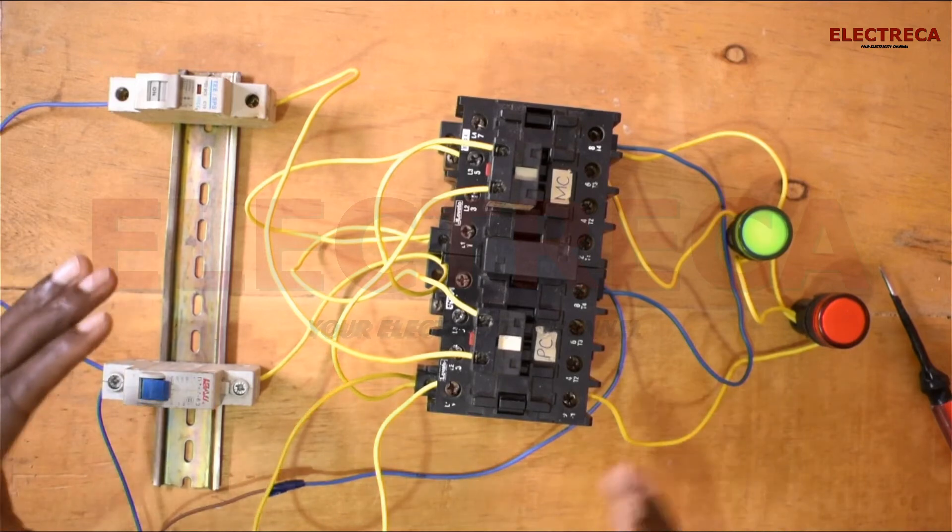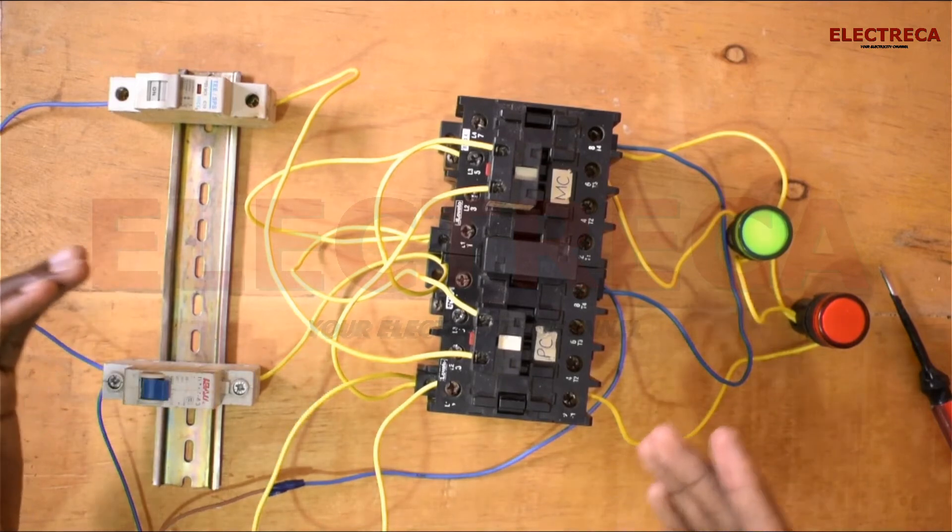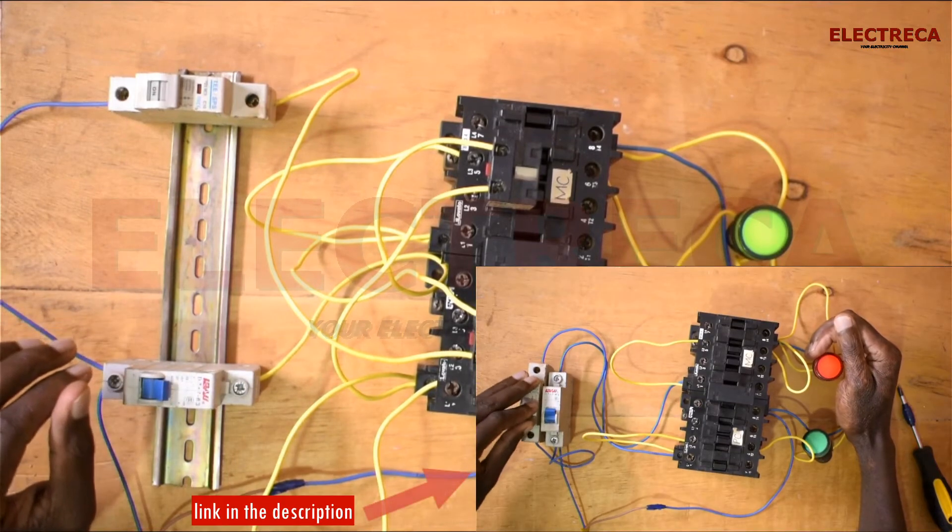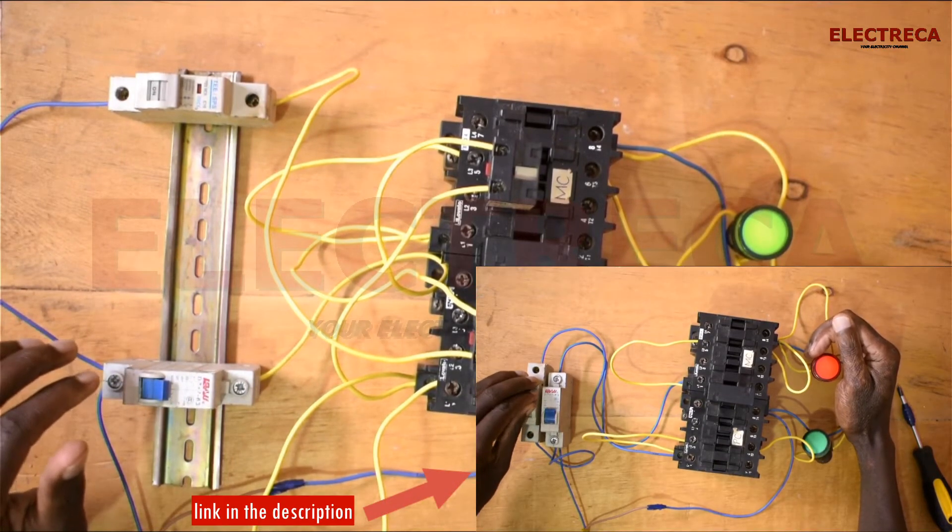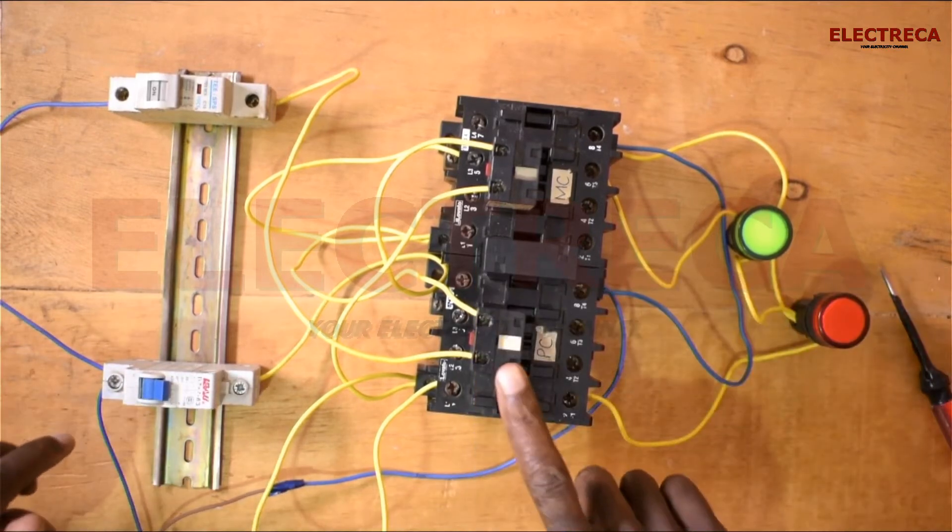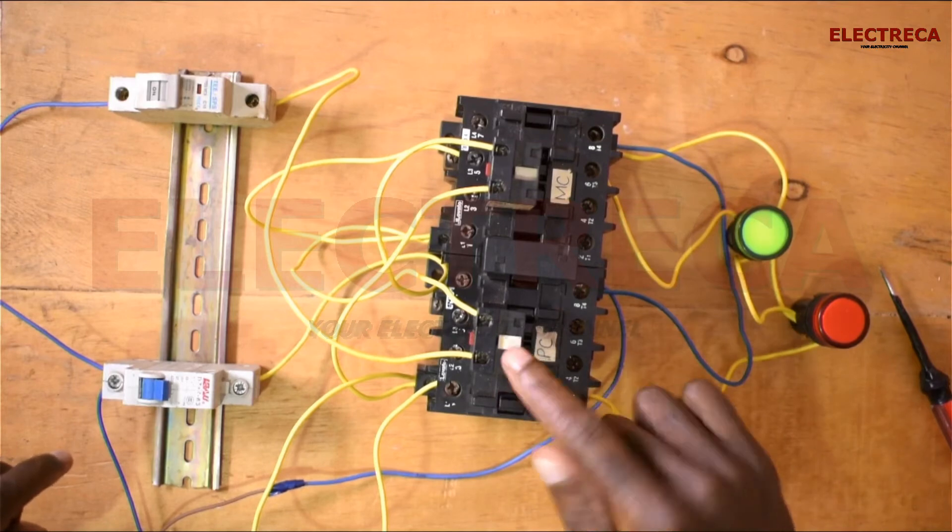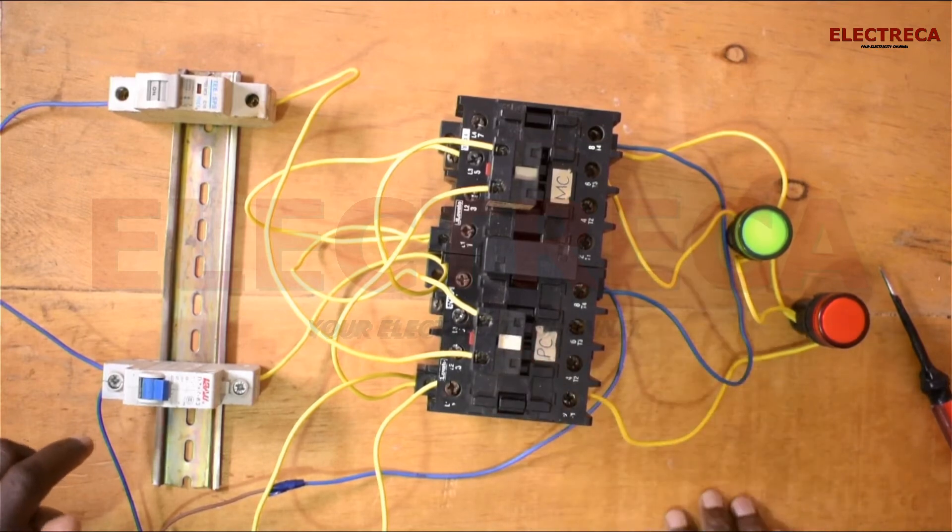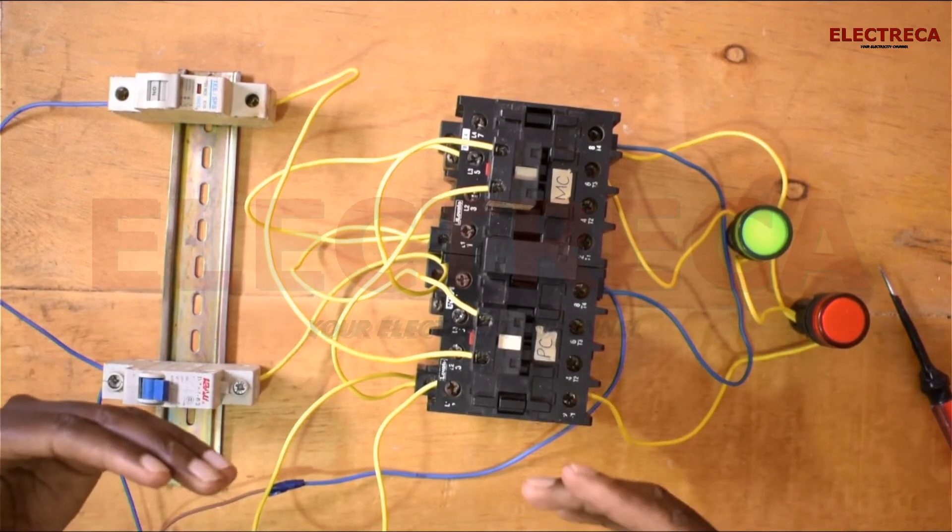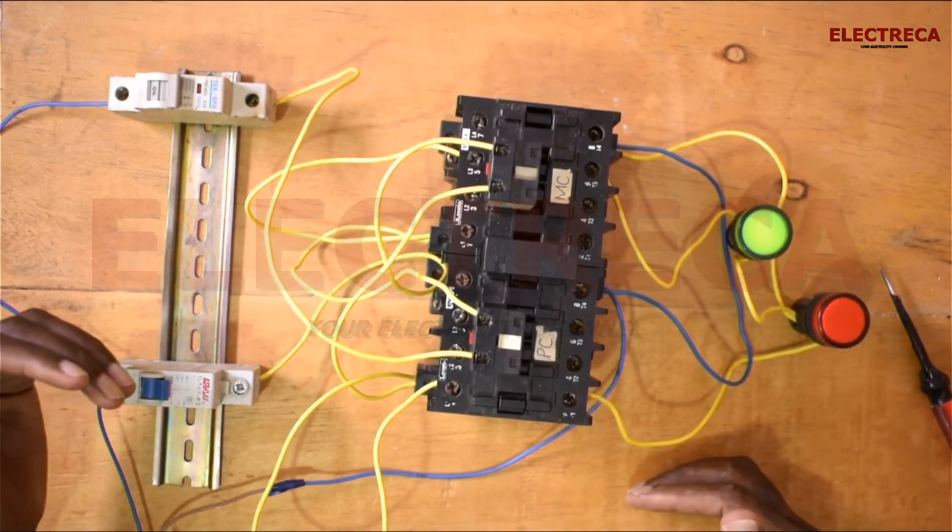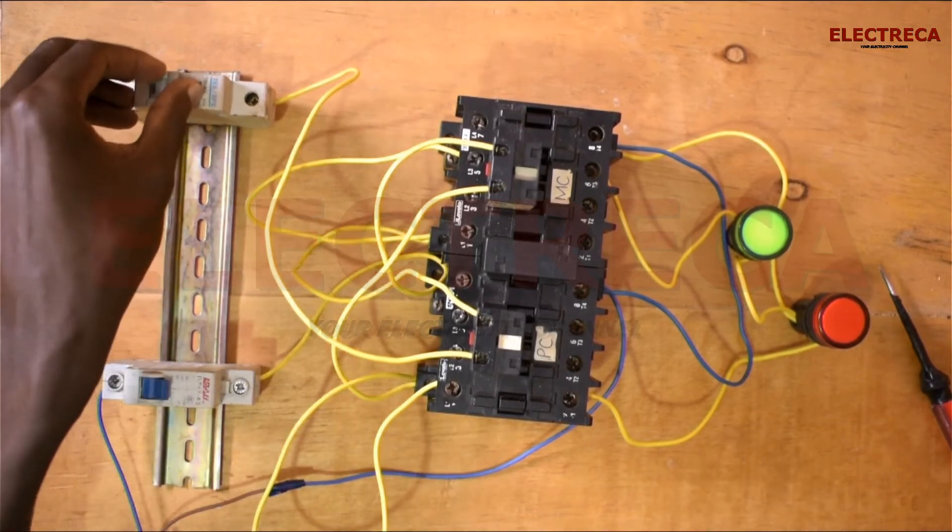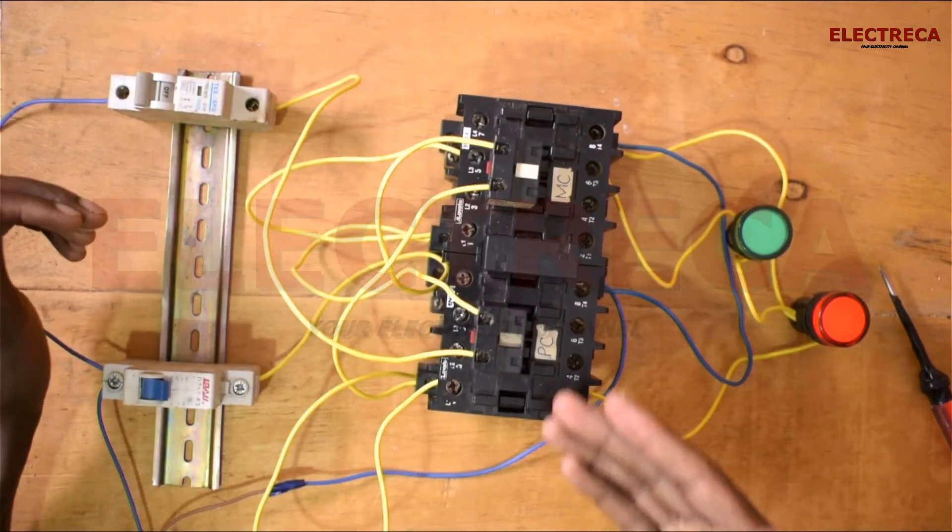When we were talking about interlock, we realized that when we engage both contactors, you see that one contactor is energized and the other one is struggling. The coil struggles to energize, and I told you that can really burn the coil. But because we've now added the electrical interlock, we don't experience that because already the power to the backup contactor has been cut.